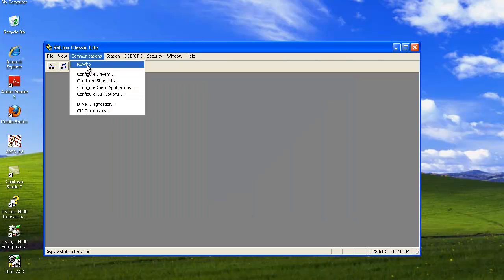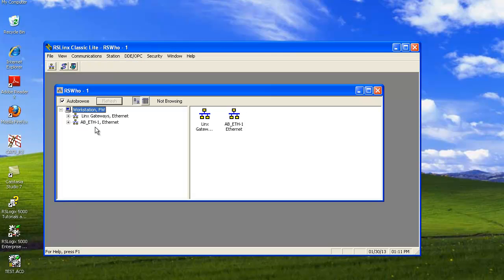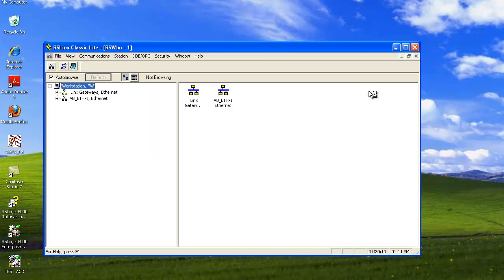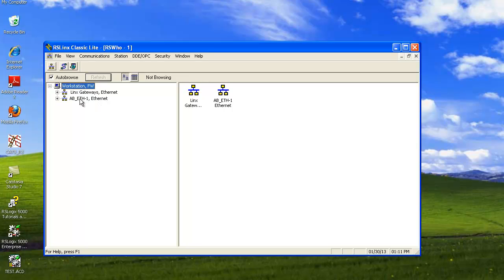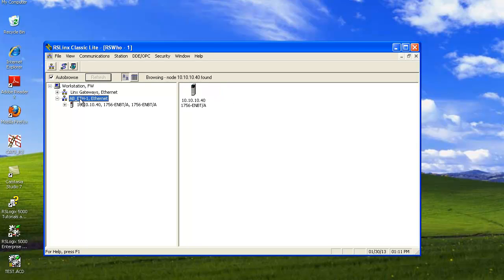Now we go to Communications and we click on RS Who. Expand this window by clicking on the square. And these are the drivers that are running. So we're going to double click on the Ethernet One driver. And you can see now it's browsing the network. It has found node 10.10.10.40 which is the actual Ethernet card.